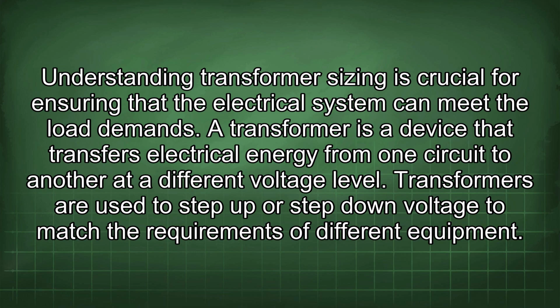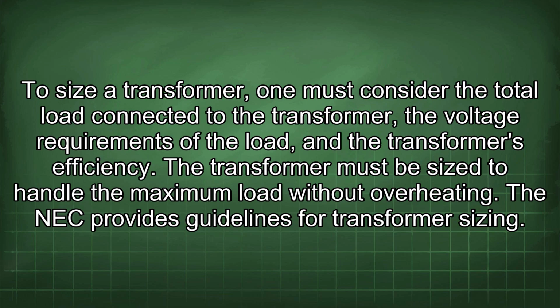Understanding transformer sizing is crucial for ensuring that the electrical system can meet the load demands. A transformer is a device that transfers electrical energy from one circuit to another at a different voltage level. Transformers are used to step up or step down voltage to match the requirements of different equipment. To size a transformer, one must consider the total load connected to the transformer, the voltage requirements of the load, and the transformer's efficiency. The transformer must be sized to handle the maximum load without overheating. The NEC provides guidelines for transformer sizing.